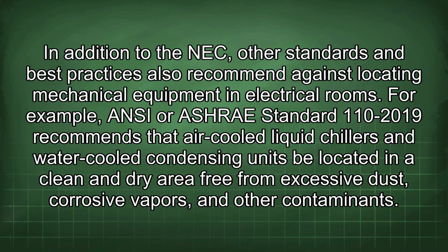In addition to the NEC, other standards and best practices also recommend against locating mechanical equipment in electrical rooms. For example, ANSI or ASHRAE Standard 110-2019 recommends that air-cooled liquid chillers and water-cooled condensing units be located in a clean and dry area free from excessive dust, corrosive vapors, and other contaminants.